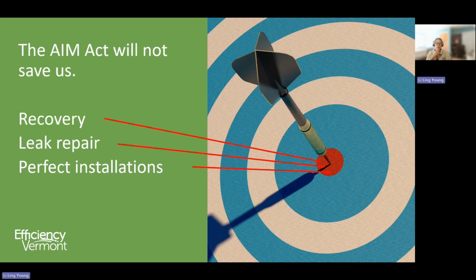The transition to lower GWP refrigerants is not going to save us. The most important work in limiting the climate impact of refrigerants is repairing leaks in existing systems and recovering legacy refrigerants. Leak-tight new installations is going to make sure we don't have the same urgency about R454B and R32 that we now have about R22 and R410A.